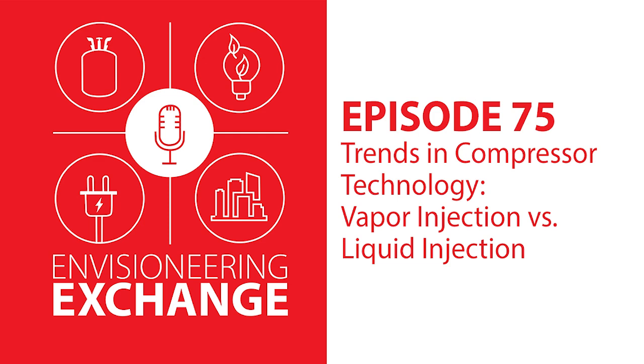And I guess the superheat software that you would use, say, feeding an expansion valve into an evaporator, you're not going to want to use that same algorithm to feed your compressor, right? Because you're looking to optimize two different things there. You're still going to have a superheat valve and an algorithm, but for sure it's going to be tweaked for the liquid injection only. And the other play of that is that when we talk about vapor injection, we're not necessarily talking about just vapor, right? Because the same compressor can do vapor, liquid, or a wet injection, which is a combination of vapor and liquid essentially. So the controller needs to be able to decide when to move into those different regions.